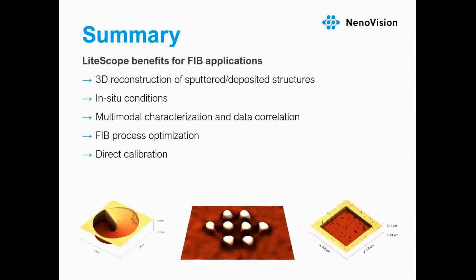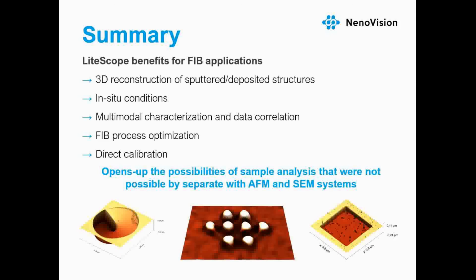Besides topography, LiteScope supports a variety of measurement modes and hardware data correlation using the unique CPEM technology for multimodal sample characterization and correlation of such data. As we have seen in the presentation, the AFM topographic analysis can be used to optimize the focused ion beam milling process and to correct roughness for heterogeneous materials or for samples with more complex surface topology. And lastly, the majority of the presented application examples show that the addition of complementary AFM to FIB-SEM systems is way more powerful than each of those techniques separately, and that these applications could not have been accomplished otherwise.